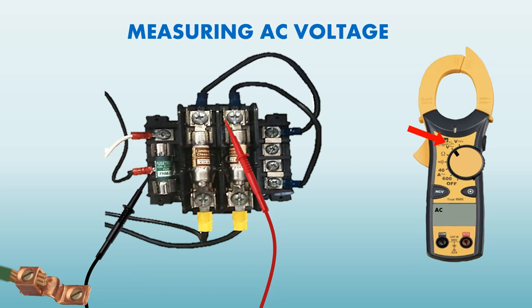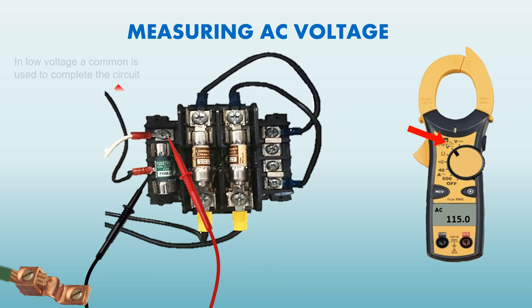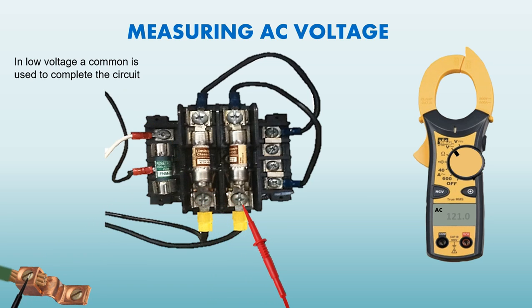To test low voltage out of a transformer, we would put 1 meter lead on the voltage or the hot leg, the 2nd meter lead on a common. When testing low voltage in our dish machines, connecting to a white wire anywhere in the machine will complete the circuit. If you are testing each individual leg on hot voltage, 1 meter lead goes to ground and 1 to a hot leg. Test the 2nd hot leg to ensure that we have the correct voltage.